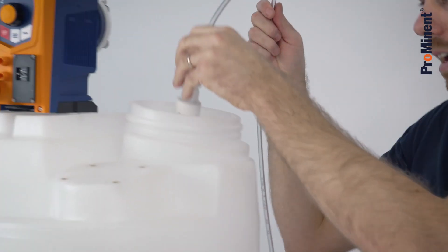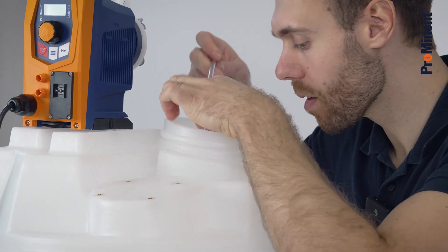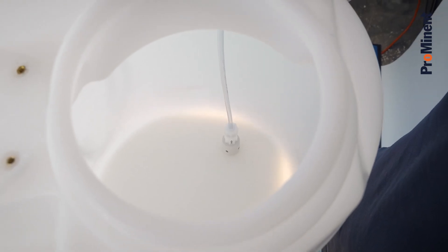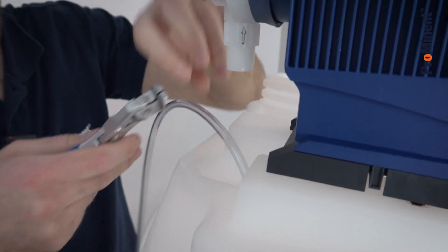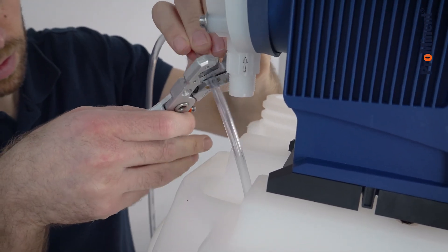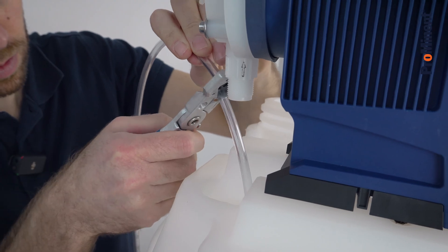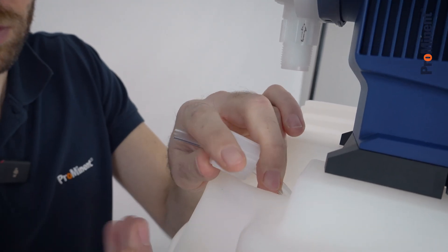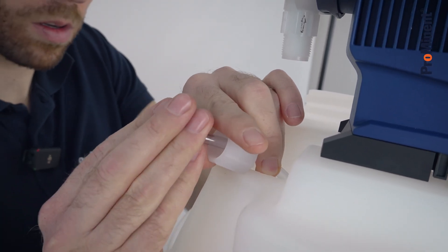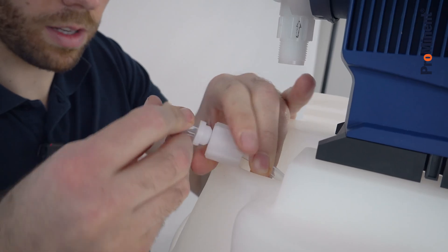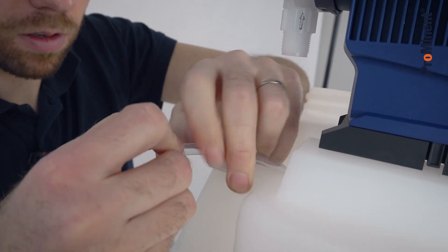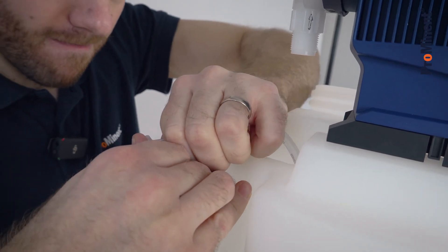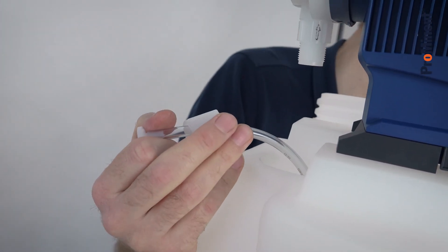Now you put the foot valve in the tank. It must be on the bottom of the tank. Now cut the suction tube to the desired length and connect it to the suction side of the pump. Now last but not least the nozzle. Don't forget the sealing.